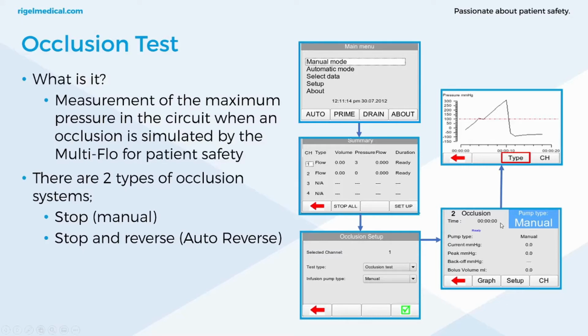So once the infusion device has either stopped or stopped and reversed, then it will be displayed on screen, and you can capture that using the green button on screen. So you'll actually capture the value, or if it's stopped and reversed, it will automatically reverse the pressure, and it will be captured within the Multi-Flo automatically. So there's two different types of systems.